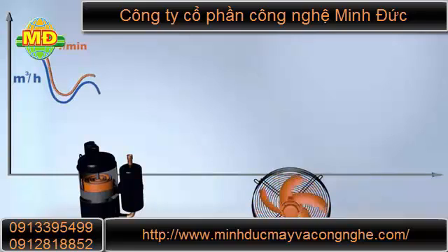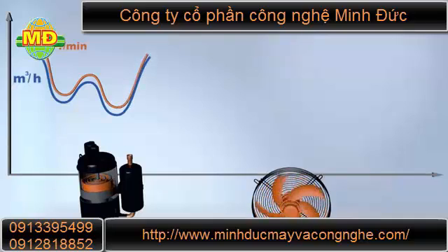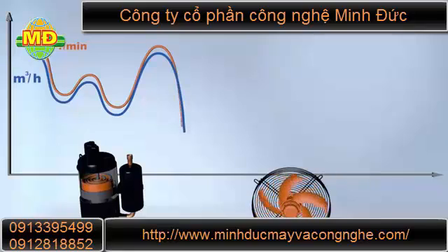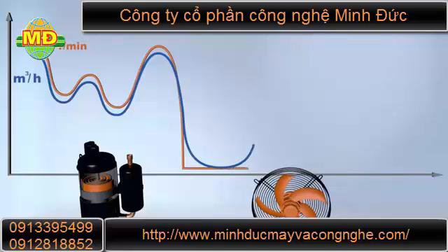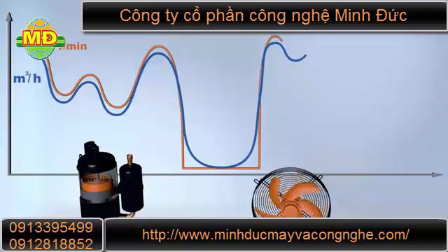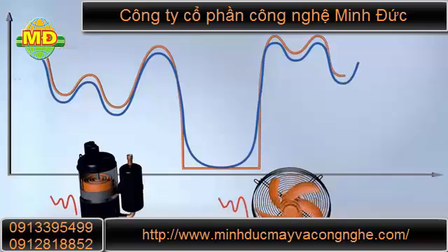smaller versions of the Drypoint RA eco switch the refrigerant compressor on and off to accommodate variations in the drying requirements. After reaching a certain system size, the drying performance is controlled by changing the frequency of the compressor, and thus even more finely adjusted to the volume flow. Larger dryers adapt both the speeds of the compressor and the fan to match the volume flow.